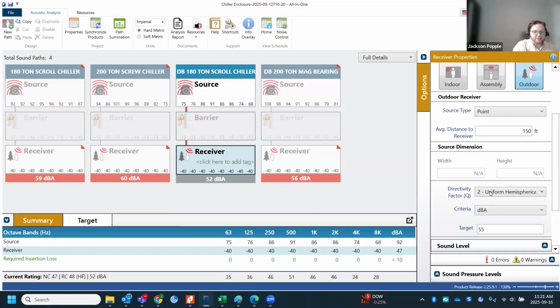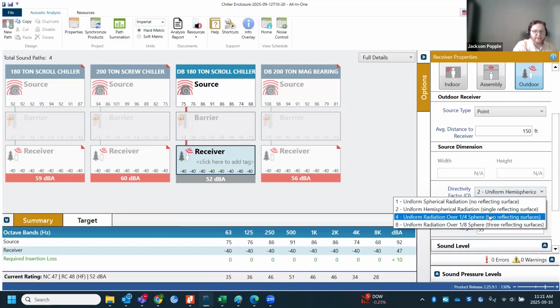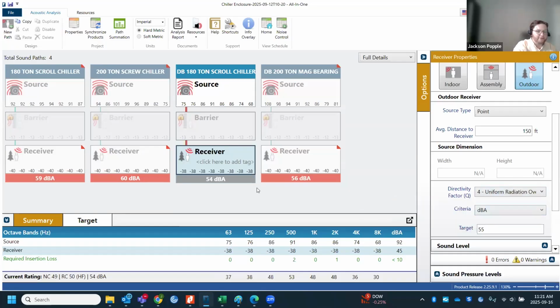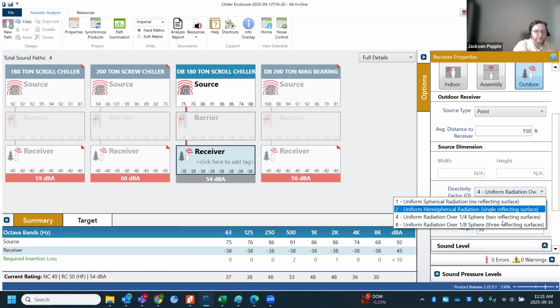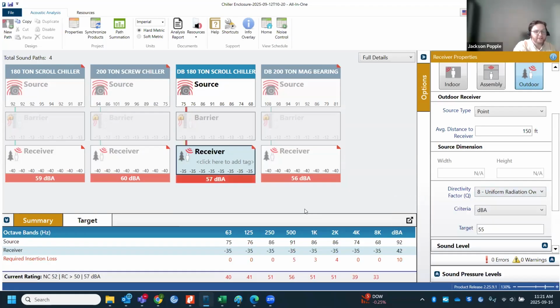The reason we might want to do that is if we go in and look, now we're at 54 dB. If we change it to a directivity factor of 4, or 2 reflecting surfaces, we're at 57 dBA. So that's a 5 dBA change, just depending on where this is installed and what's around that chiller.